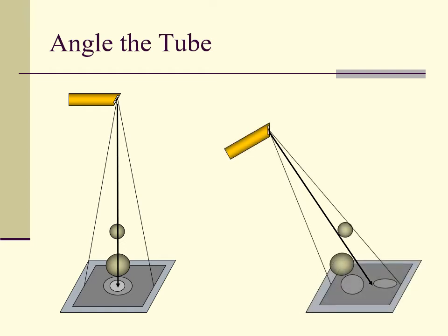This slide illustrates the effect angling the tube has on the final image. One should note that the image of the large ball, which is closer to the image receptor, is much less elongated and isn't shifted to the right as much as the small ball. Objects with a large object-to-image distance will distort more, and their image will move more relative to the image receptor when the tube is angled.